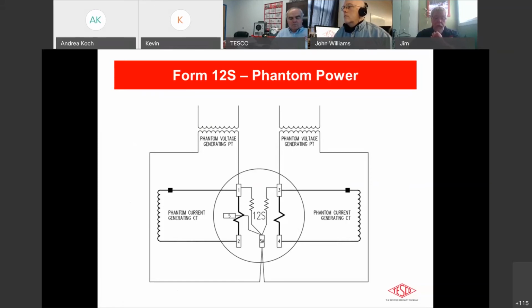So the meters are arranged so that apartment 1 gets its energy from phase A and phase B, apartment 2 gets B and C, apartment 3 gets A and C, and so on up the building. And they do it that way so that it eventually balances out the three-phase load. So they're drawing from different phases of the four-wire arrangement, three-phase four-wire. Yeah, here too in the States, I think the most common application I heard of is just like Jim said, in big apartment buildings, condominiums, etc., where the balancing of the three-phase load is easily done applying the 12S meter in the arrangement that Jim mentioned.